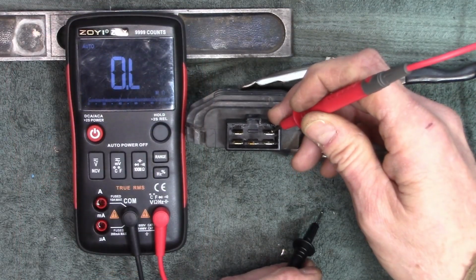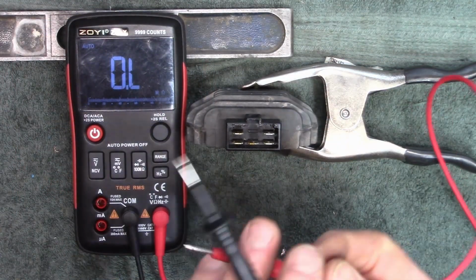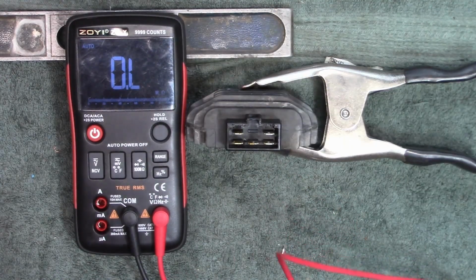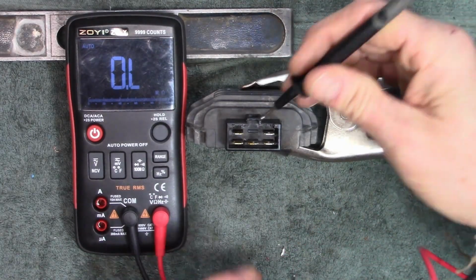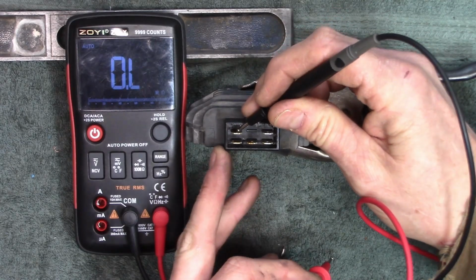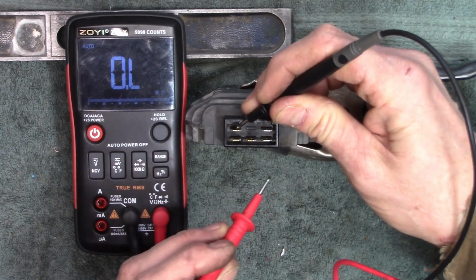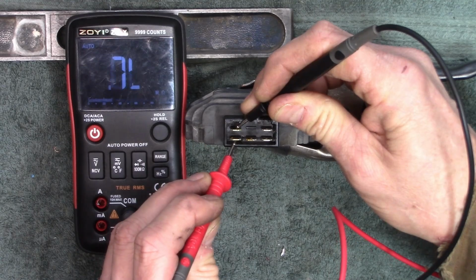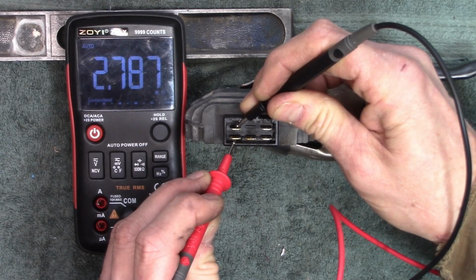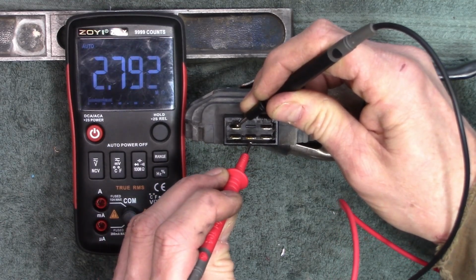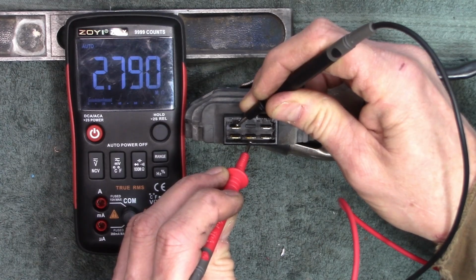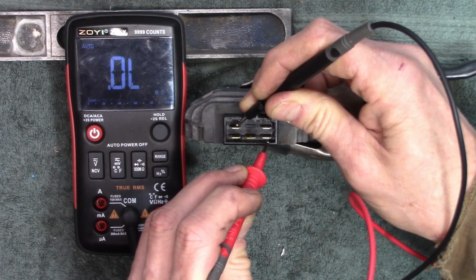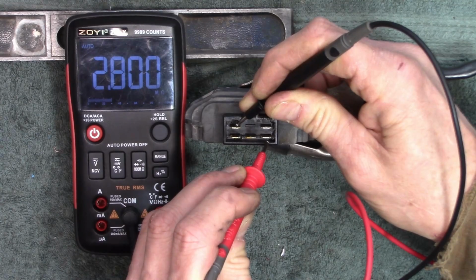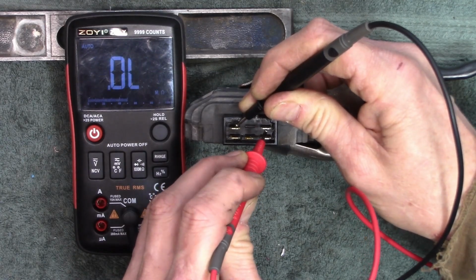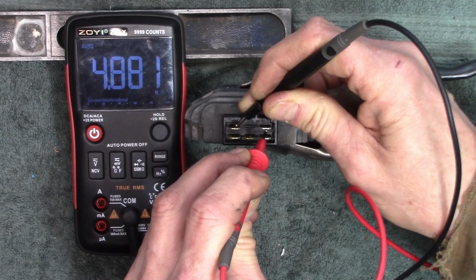Next, I'm going to switch and use my black probe on the R connector up top here, and go all the way around again. 2.7, that's within spec. 2.7 again, that's within the 1 to 10 range, and that is within range as well. If I probe up here, I get 4.8, which is exactly in spec.